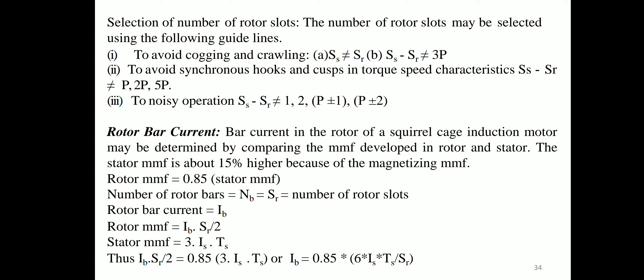Rotor bar current is determined by comparing MMF developed in rotor and stator. The stator MMF is about 15% higher due to magnetizing MMF, so rotor MMF = 0.85 × stator MMF. Number of rotor bars Nb = Sr. Rotor MMF = Ib × Sr / 2. Stator MMF = 3 × Is × Ts. Thus: Ib × Sr / 2 = 0.85 × 3 × Is × Ts, giving: Ib = 0.85 × 6 × Is × Ts / Sr.